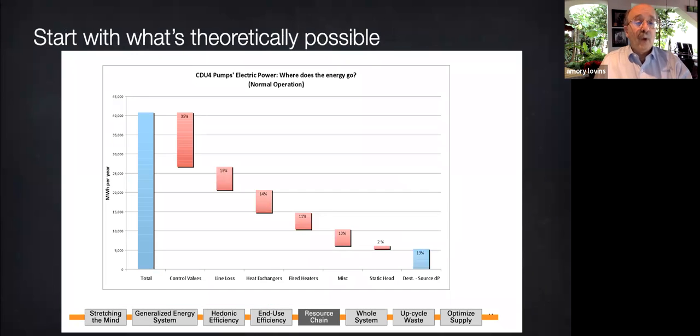Now, he asked where the pumping energy goes, and he found fat opportunities to wring a lot of it out. Notice that only a small fraction of the pumping power was overcoming pipe friction, which could in turn be greatly shrunk.